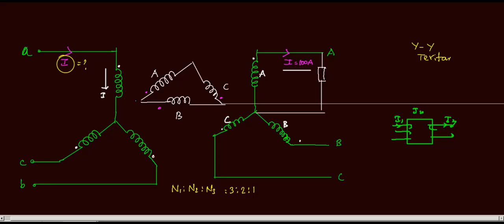But you see here, phase A MMF is balanced, while phase B and phase C MMF is not balanced, because in the secondary winding there is no current there due to unbalanced load. So for that purpose MMF balance is not achieved in phase B and phase C. For this balance condition, I am placing a tertiary winding.